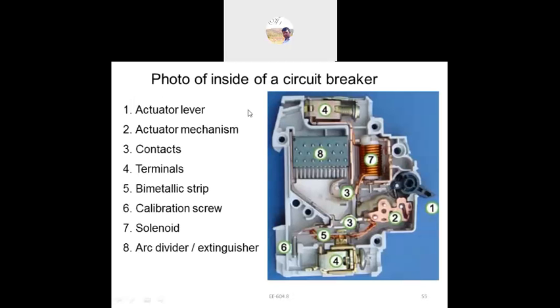Here we can see a circuit breaker, this is the MCB. You can see the actuating lever, which is used to open or close, and the electromagnetic mechanism. This is the actuating mechanism: either open, reset, or close, and the contacts connected here with a coil. You can see the input contacts and outgoing contacts. Here is the bimetallic strip, connected in line, and the calibrated screw, which sets how much current can flow. Here is the solenoid, which is an electromagnet, and the arc divider. So this is the MCB.